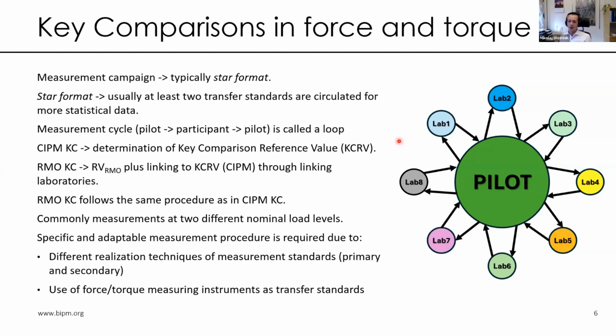And in order to have good comparable measurement data, we apply a specific procedure which can be adapted to different so-called machines that we use to realize and generate force and torque. So these are the different measurement standards. Usually they are primary types, but also secondary.